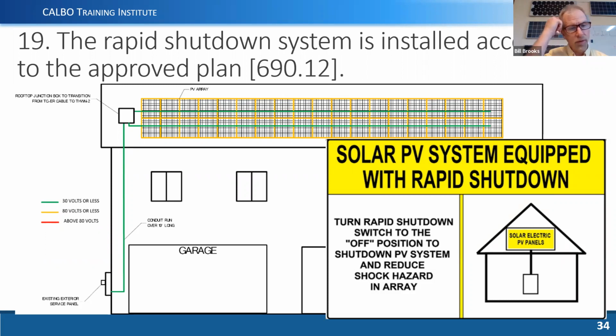And here's an example. This particular example is a microinverter system where we have modules and microinverters up on the roof. The modules could be up to 60 or 80 volts when they're at open circuit, but the conductors coming out of the microinverters are going to be shut down to 0 volts, which is below 30, within 30 seconds. And that AC line goes directly into the service equipment on the outside of the house. So there's an example of a microinverter system. And of course, there are other methods of providing rapid shutdown compliance.